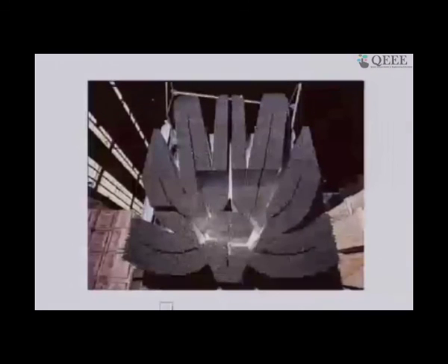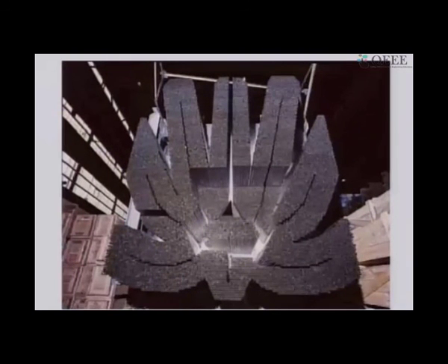This is another picture of a tube bundle layout of another power plant. And here you can see they have made a lot bigger passages for the steam to flow through. What you see is actually thousands and thousands of tubes which have been put here, and they run the full length normal to this. That length typically is about 10 meters, 15 meters, very long tubes. And so you can see that they've left a big gap here.